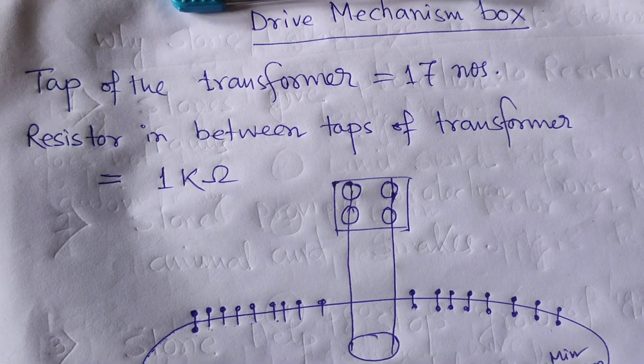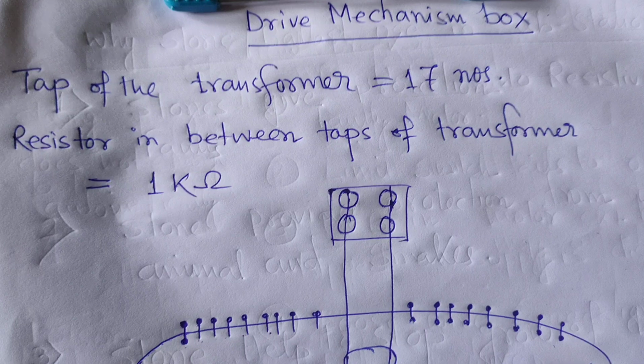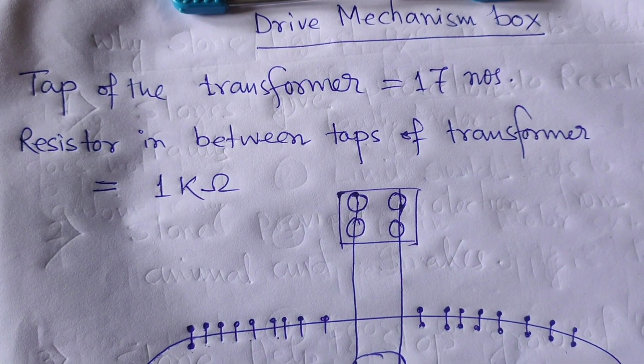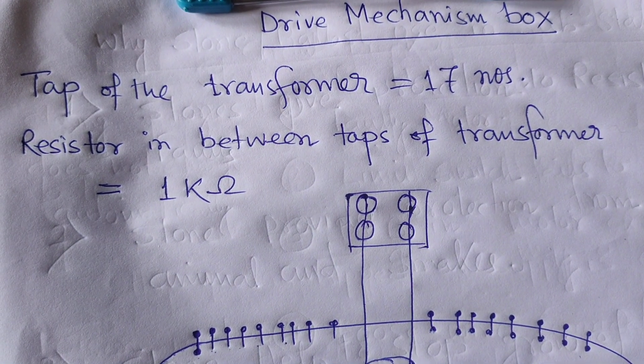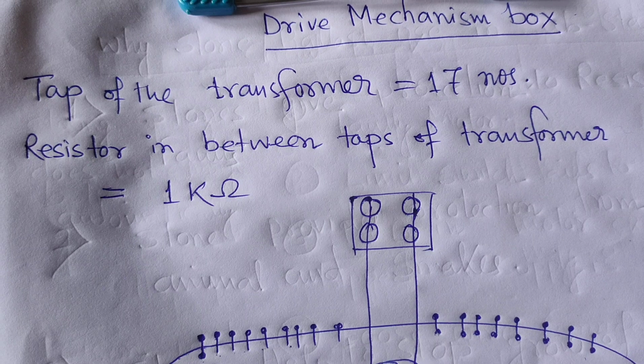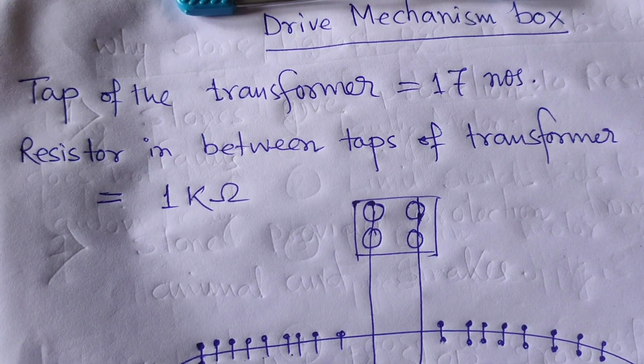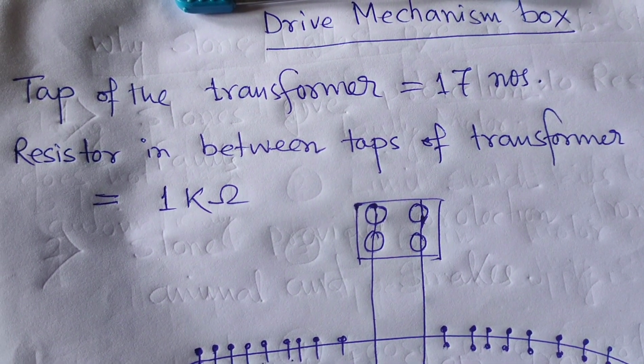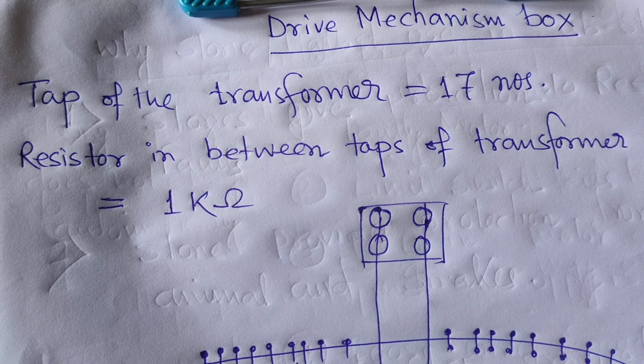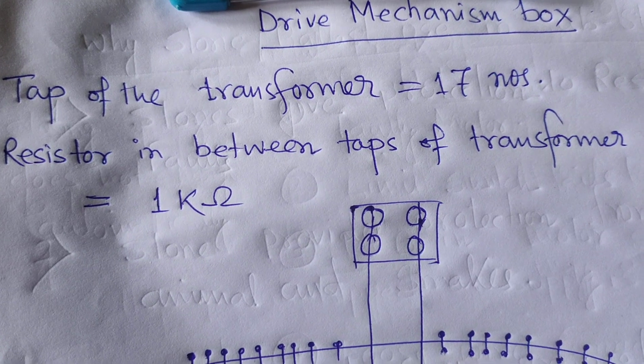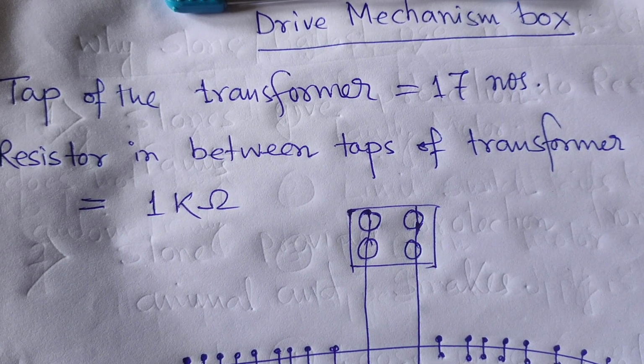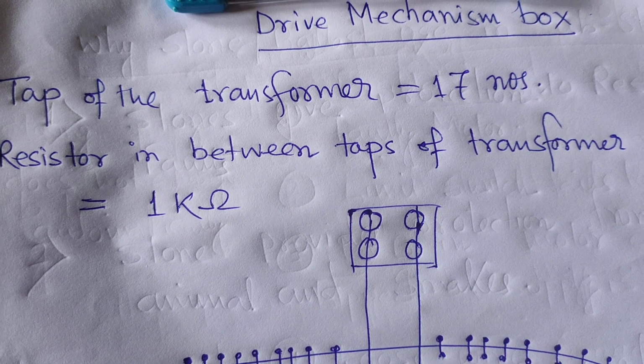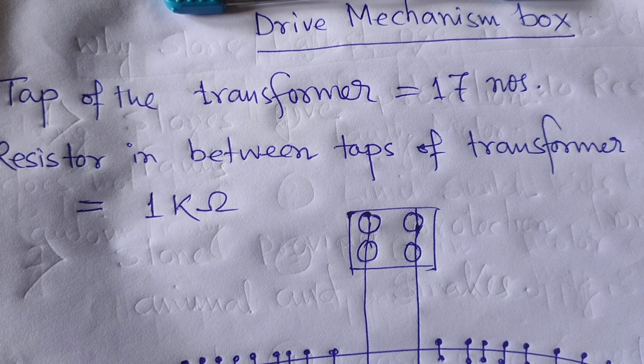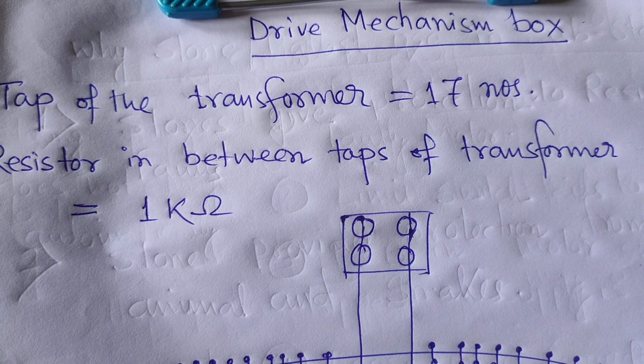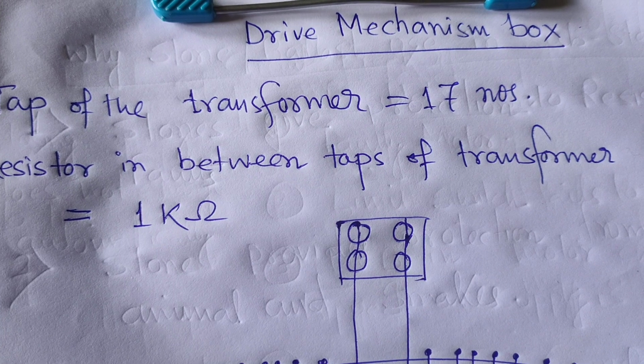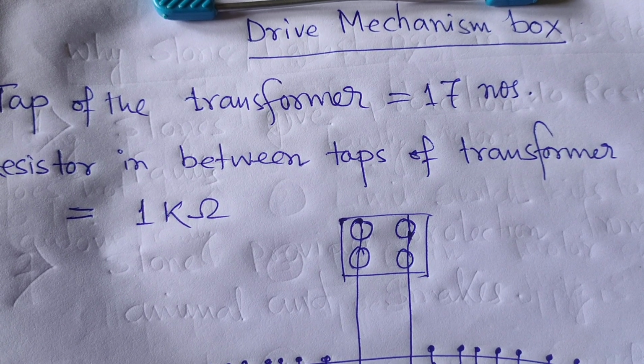Today my discussing topic is about inside the drive mechanism box. We all know that the drive mechanism box is attached with the power transformer. What is the reason behind the attachment of the drive mechanism box? The drive mechanism box has two functions. One is the on-load tap changer purpose and off-load tap changing purpose.